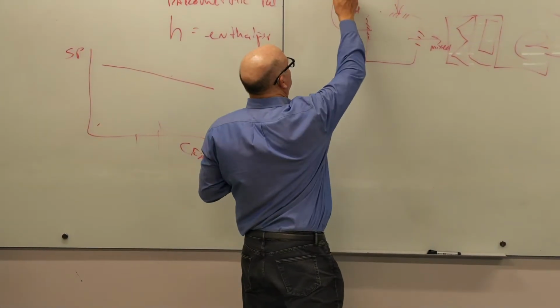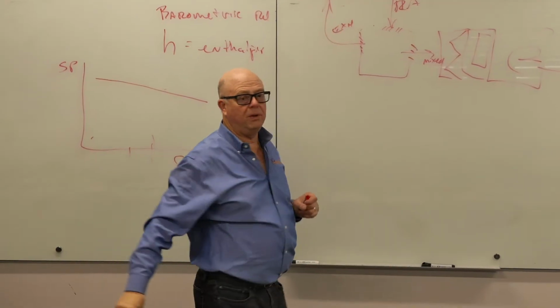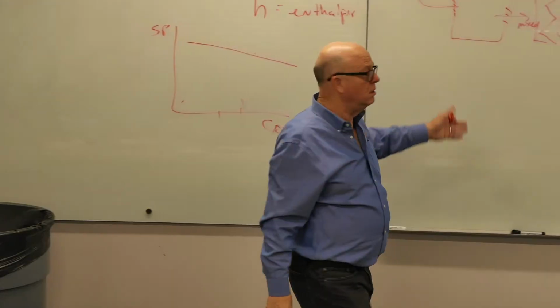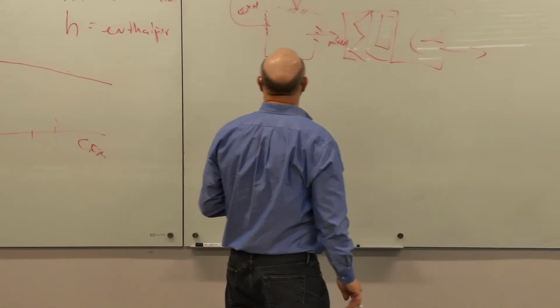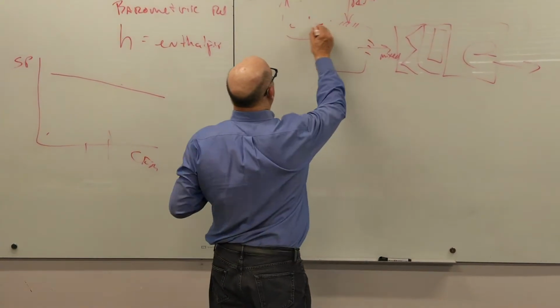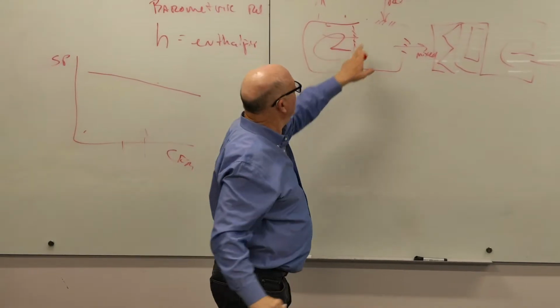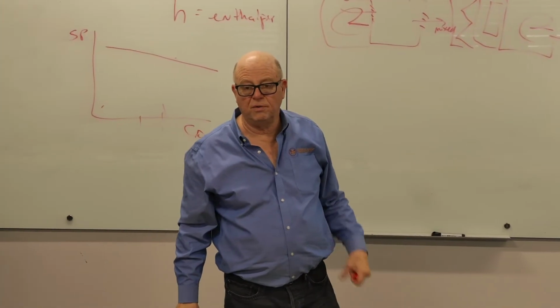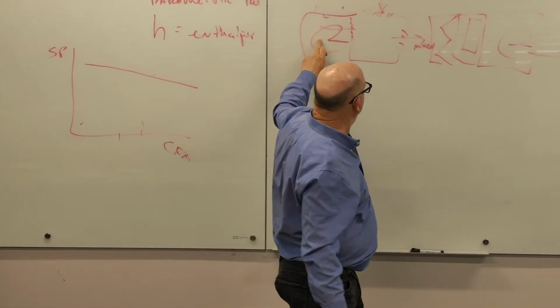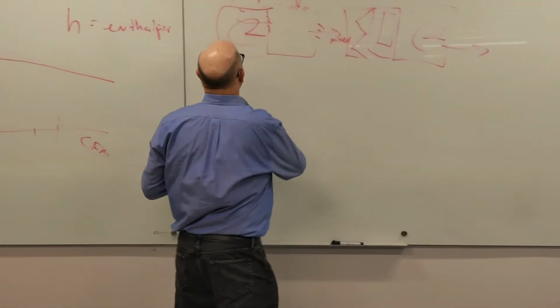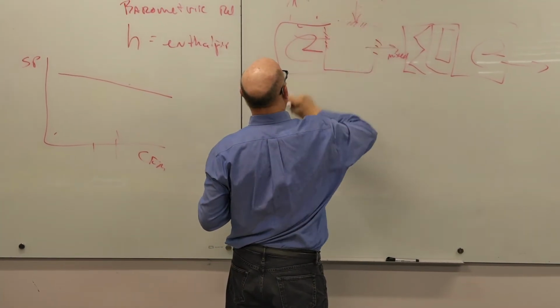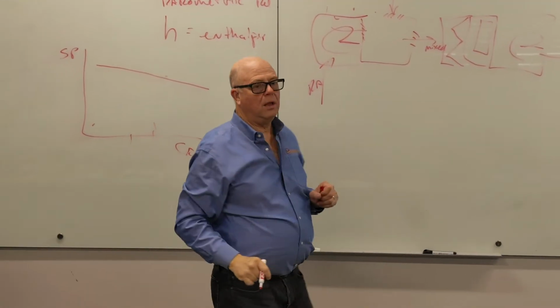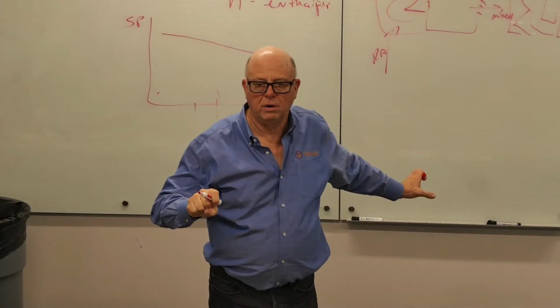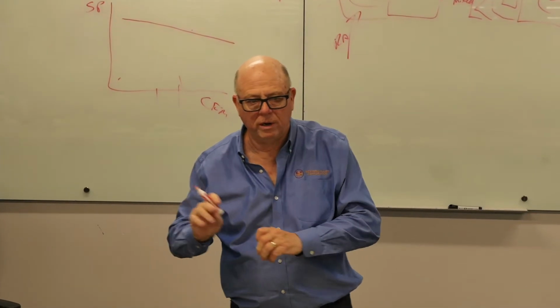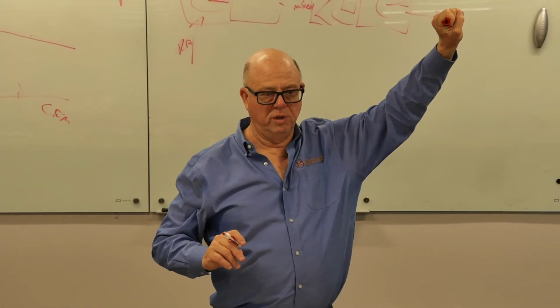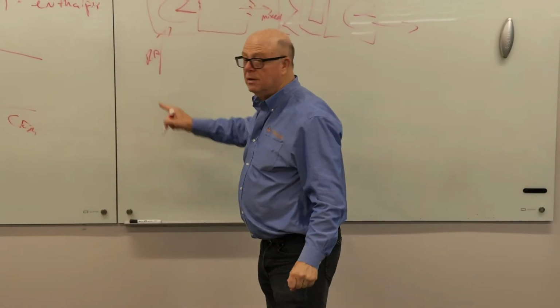So if you were going to use a relief fan, you'd have a fan here someplace blowing air, probably on the roof. You could mount it there. You could put it there. But with a return fan, what they do instead is they put one here. They have very similar logic for the fans. But what they do is they try to take return air and they are powering the return. With the relief fans, we were powering the exhaust, the relief. But a return fan powers the return.